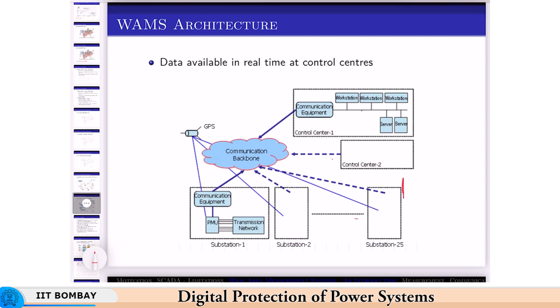So then that is taken to a control center, which could be an RLDC, SLDC of that nature, and then you have server grade equipment which acts as a PDC, that is the phasor data concentrator, and does the assembly of those synchrophasor data, and then can run analytics on them. So this is already happening. We already have about 1400 PMUs installed in India, and all the PDCs, etc. are happening. There are analytics running on the servers.